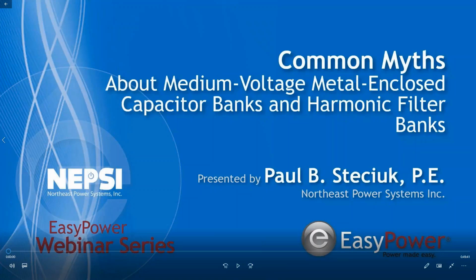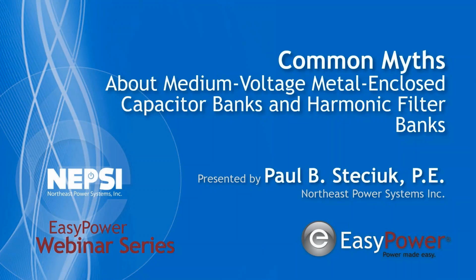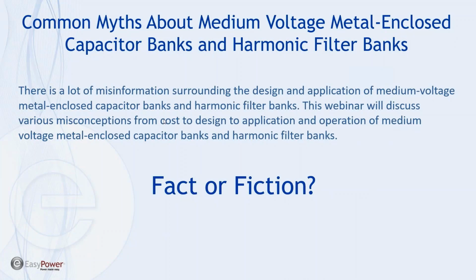Hello, everyone, and welcome to this EasyPower webinar. My name is Paul Steciuk. I'm a co-founder of Northeast Power Systems, a leading supplier of metal enclosed capacitor banks and harmonic filter banks. Today, we're going to speak of the myths in regards to medium voltage metal enclosed capacitor banks and harmonic filter banks. There's a lot of misinformation surrounding the design and application of medium voltage metal enclosed capacitor banks and filter banks. This webinar will discuss various misconceptions from cost to design to application and operation of medium voltage metal enclosed capacitor banks and harmonic filter banks. So it's a fact or fiction type of presentation. I present a statement and we determine if it's fact or fiction.